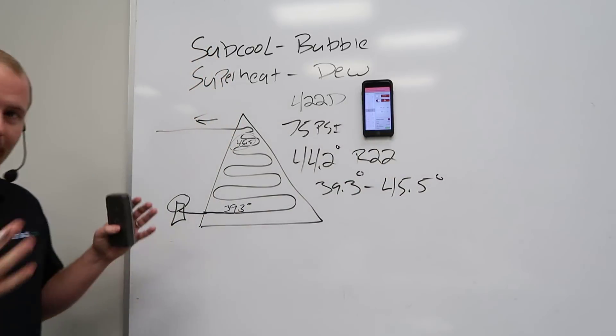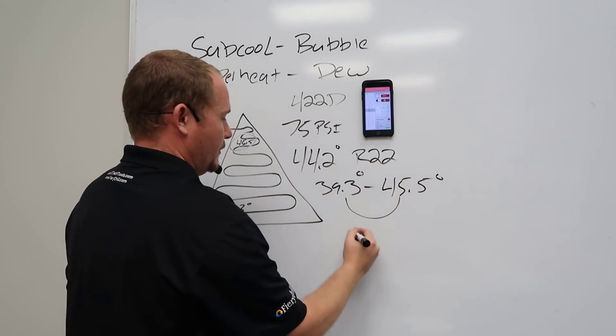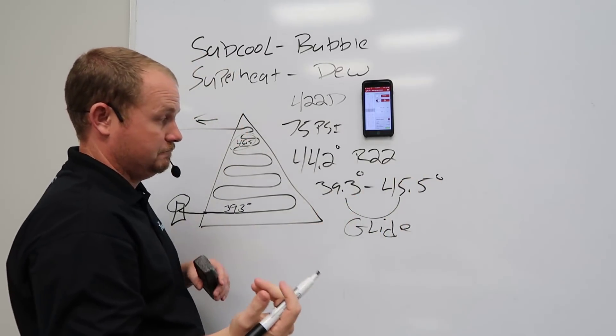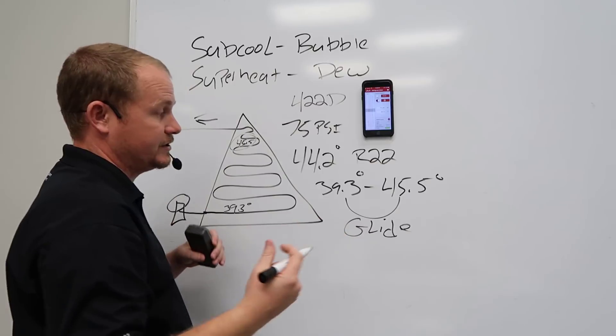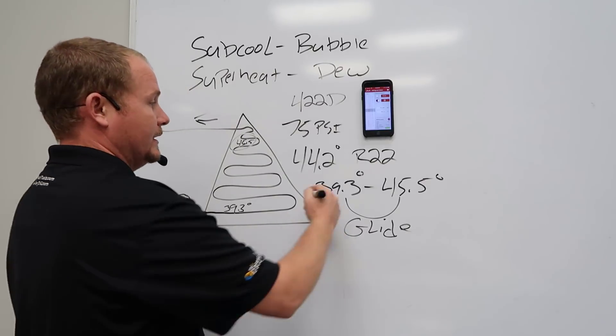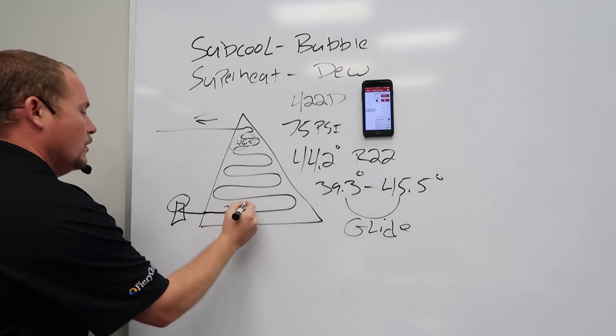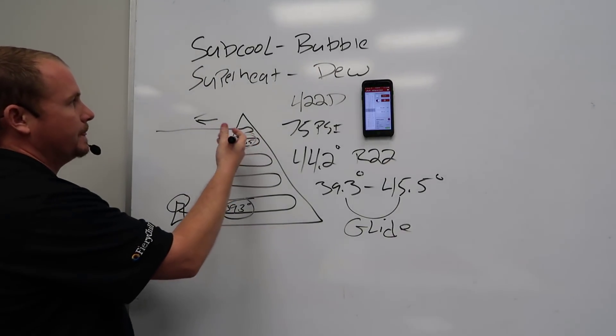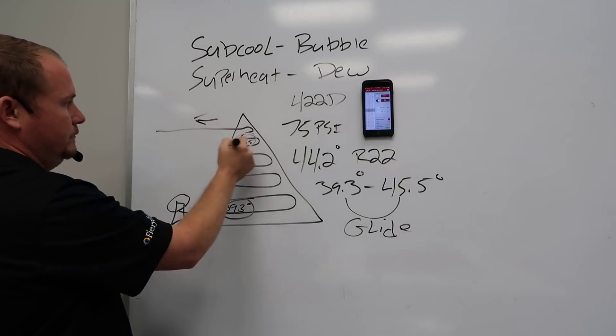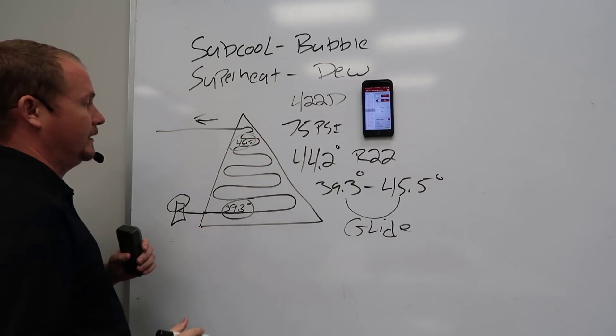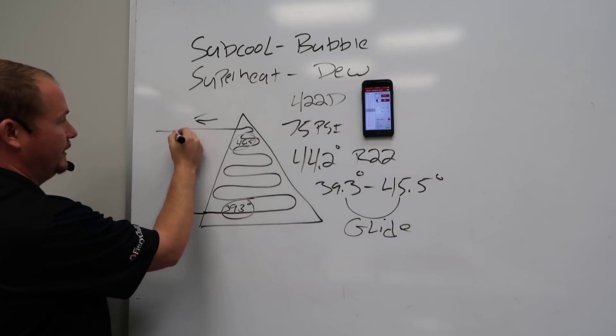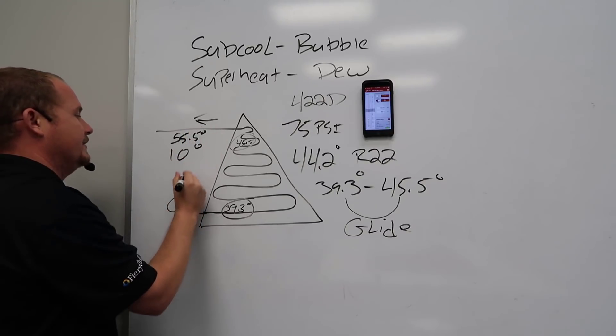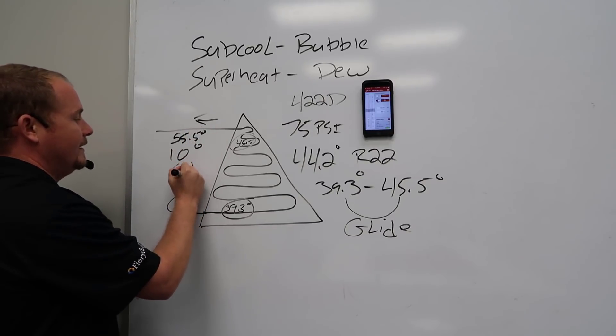So we have a range. This range is what we call glide. We have a glide of six degrees, slightly over six degrees. So that's our differential. Now when we're calculating superheat, we know that we use the dew. So this temperature here is what we use to calculate superheat. If our suction line temperature is 55.5 degrees, we would say that we have 10 degrees of superheat. And that is correct.